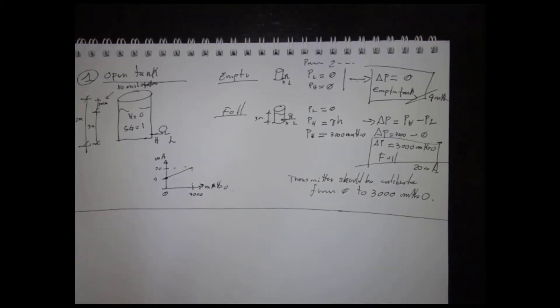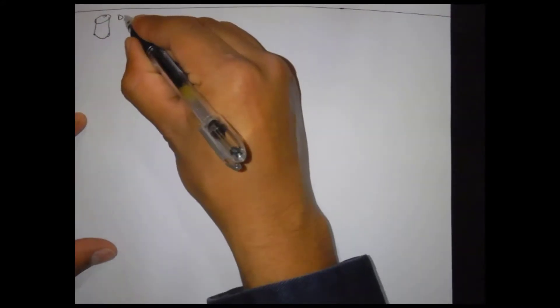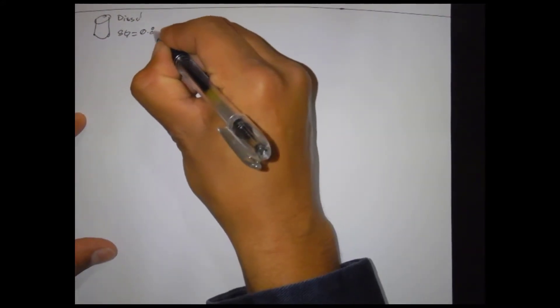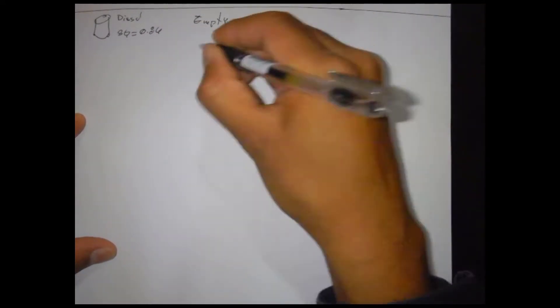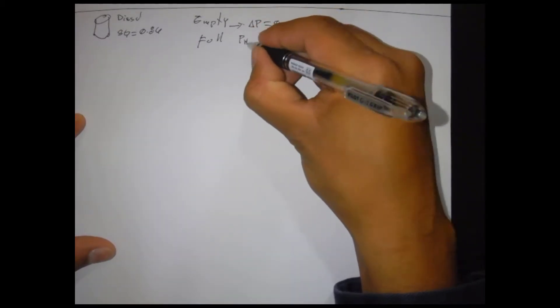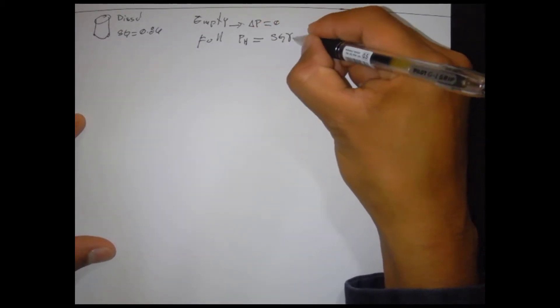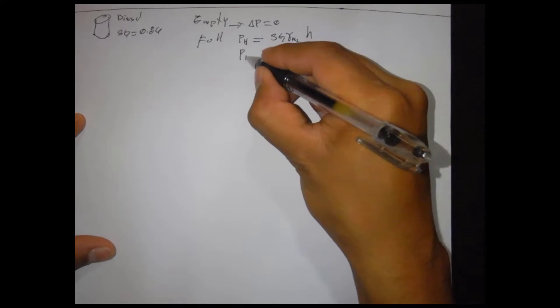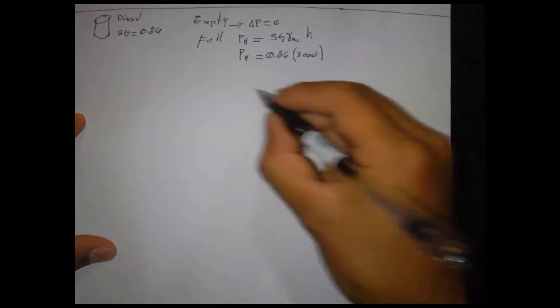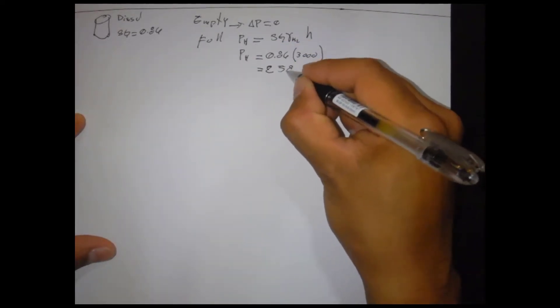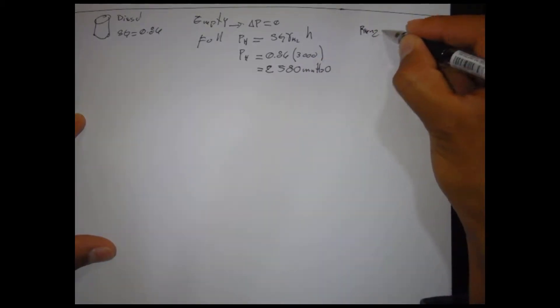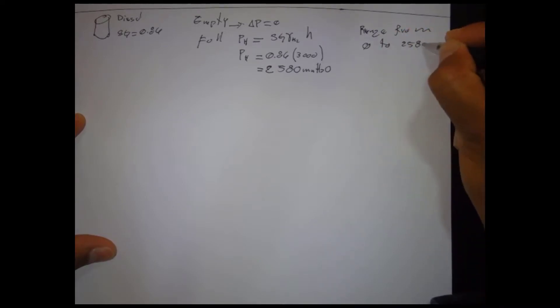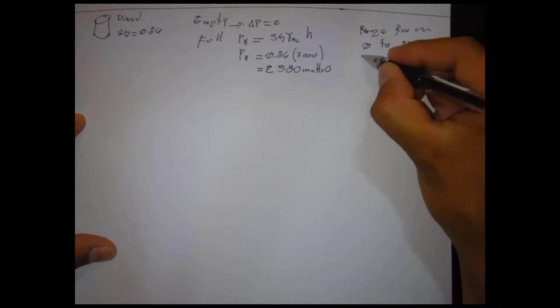We develop the same example, but in this case the tank is full of diesel. We consider a specific gravity equal to 0.86. If the tank is empty, the differential pressure read by the transmitter is zero. When the tank is full, the differential pressure will be equal to 2580 mm of water. The transmitter should be calibrated from zero to 2580 mm of water.